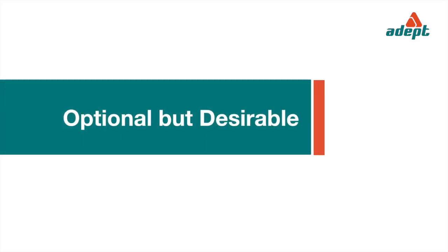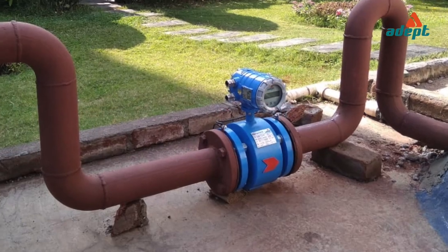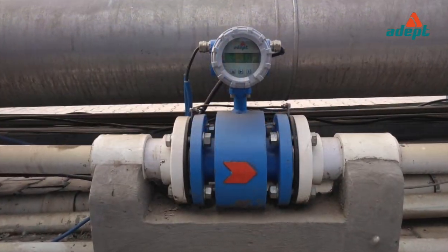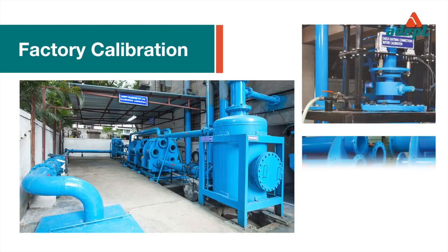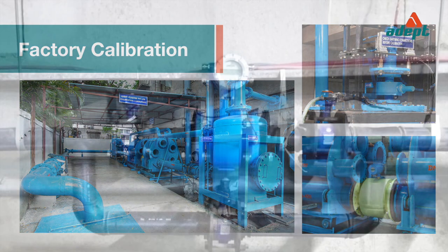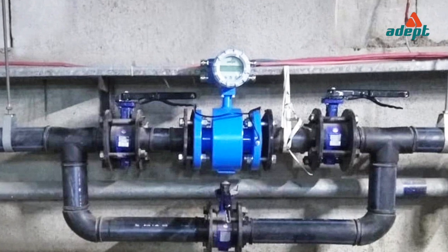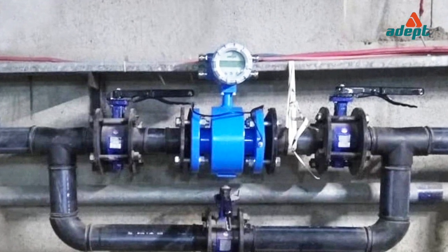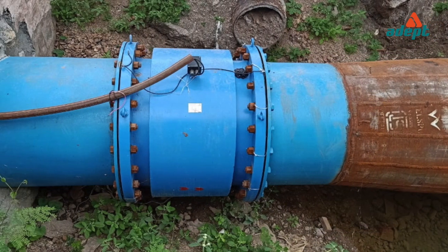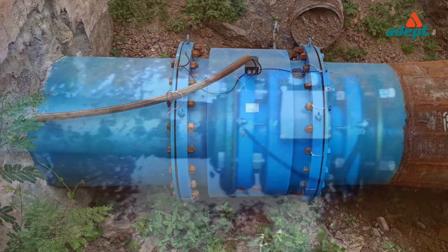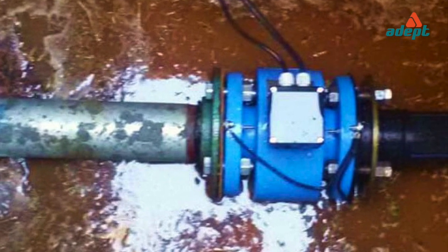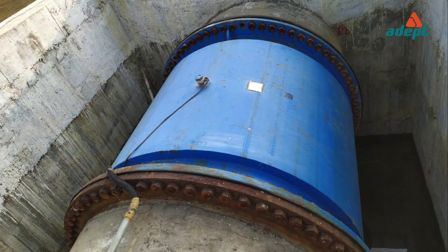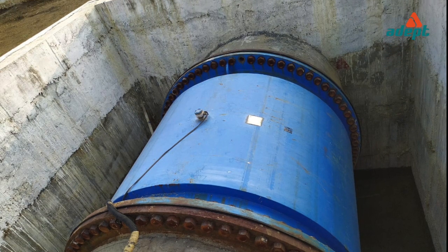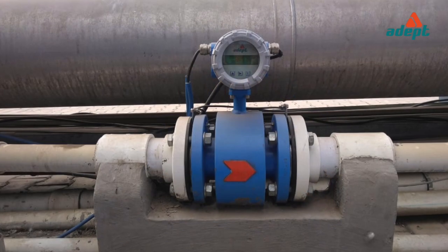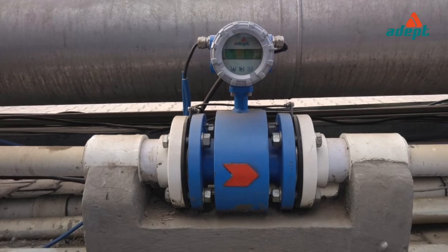Optional but desirable. Flow meters of sizes up to DN300 generally require factory calibration, so a bypass arrangement can be provided for easy removal and reinstallation. For flow meters installed at outdoor locations or underground pipelines, suitable size chambers can be constructed around the flow tube for safety and for easy maintenance.